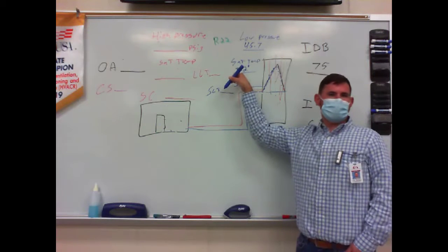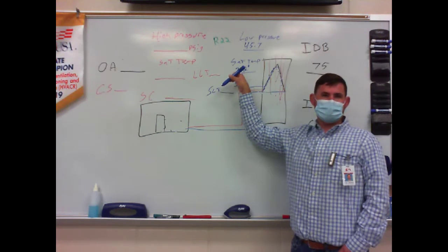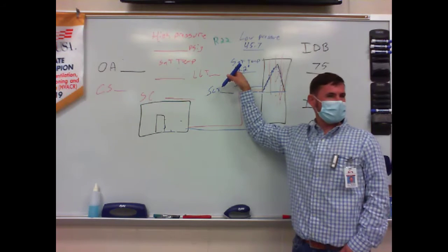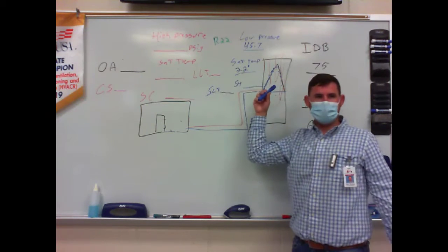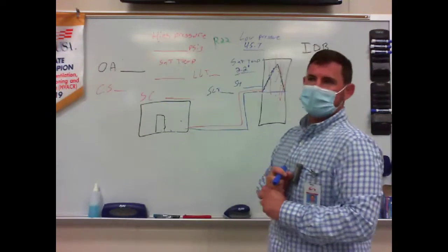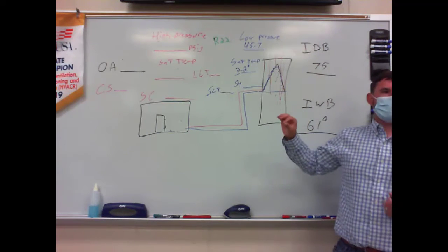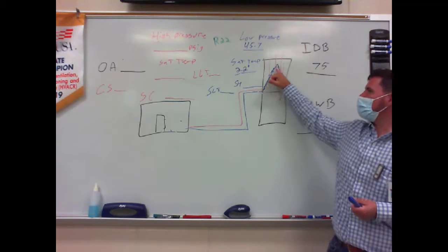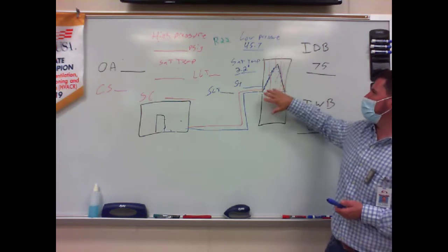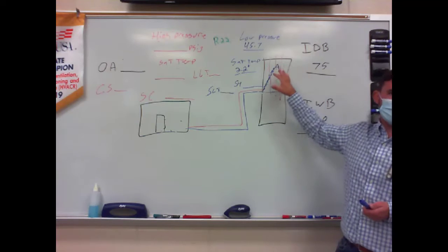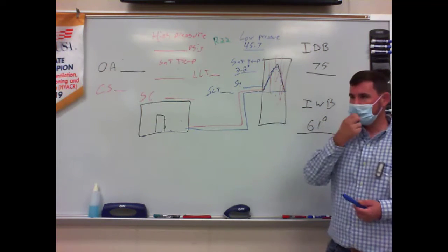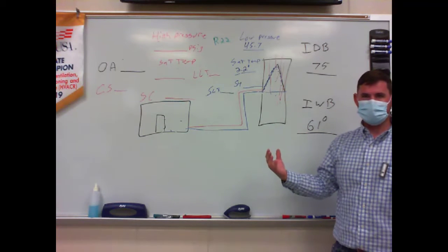Instantly, what do I know about that number? I can't be saturating at 22 degrees on an air conditioner, right? What's going to happen to my coil? That's right, it's going to freeze up. So I know that's low. So if I am undercharged, if my evaporator is starving of refrigerant, my superheat will be really high. If I'm clogged up and dirty, or I have low airflow, or my filter's jammed, my superheat's going to be really low because I'm not picking up any heat and boiling off my refrigerant.